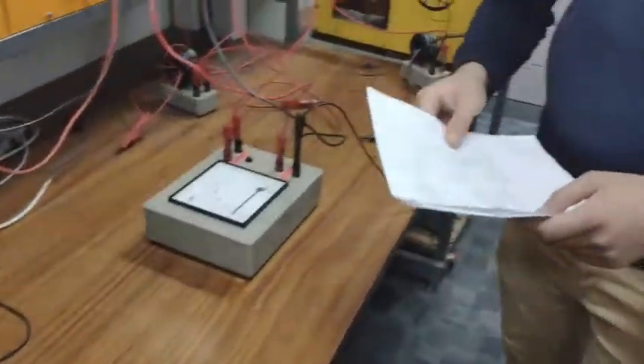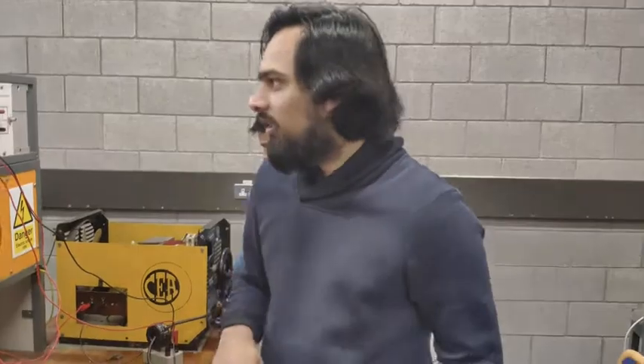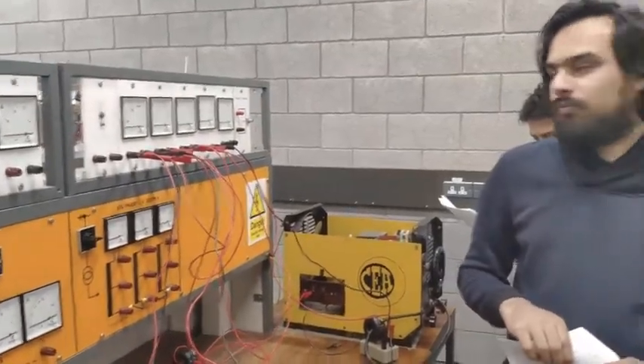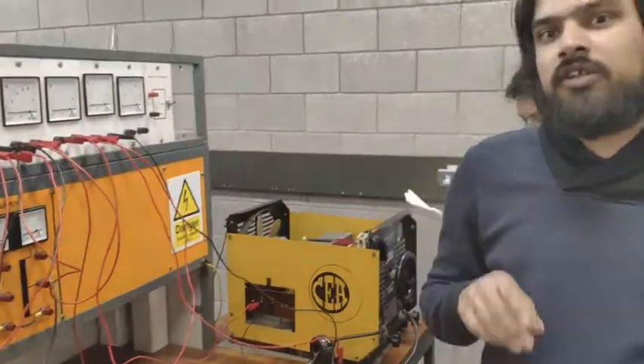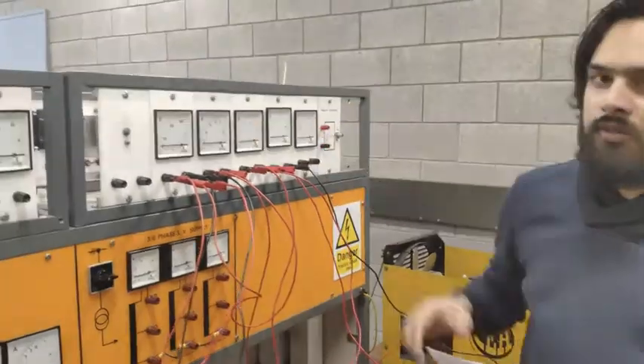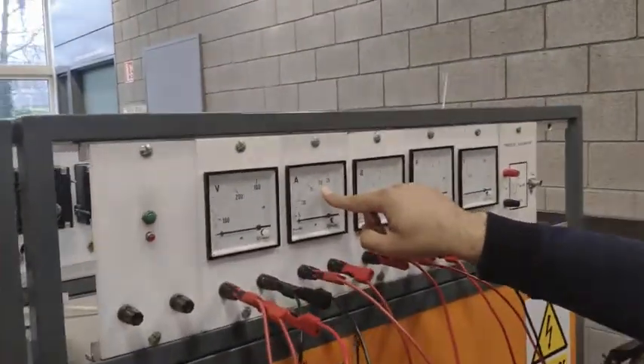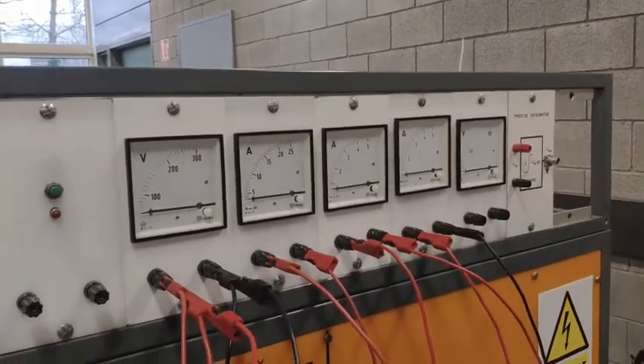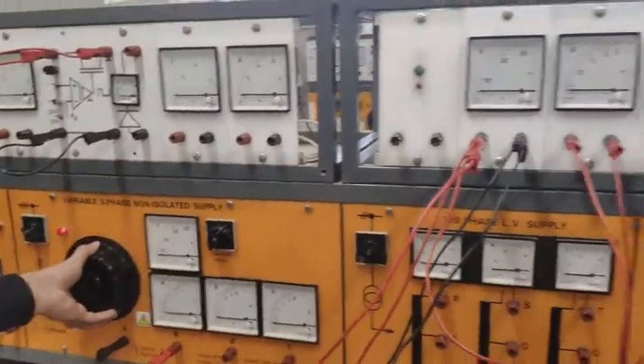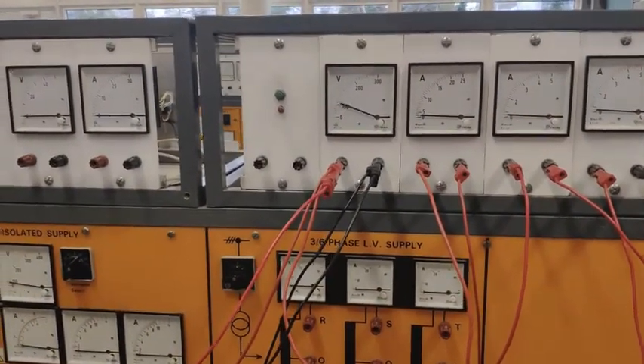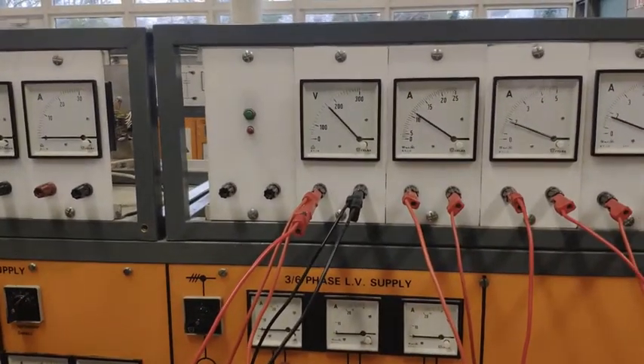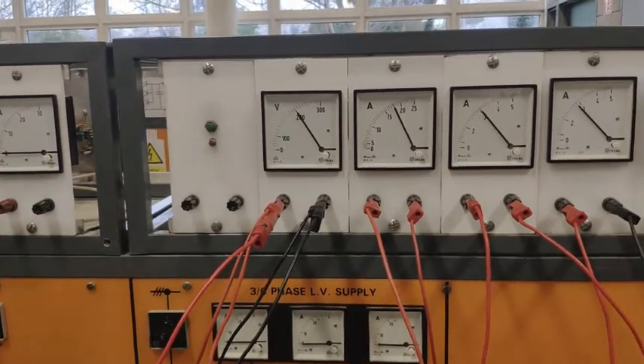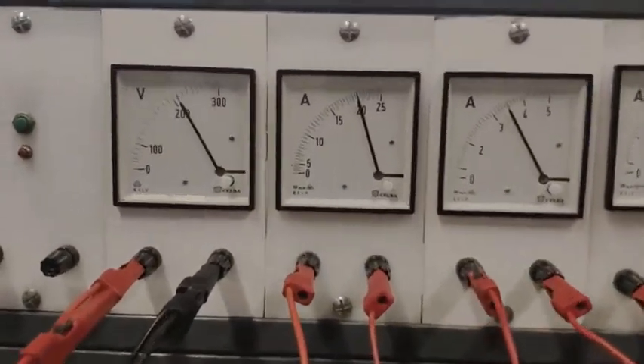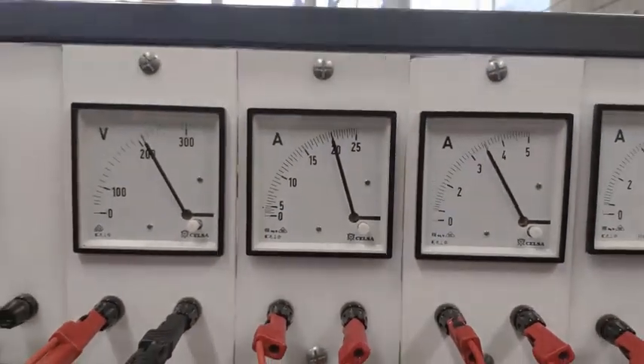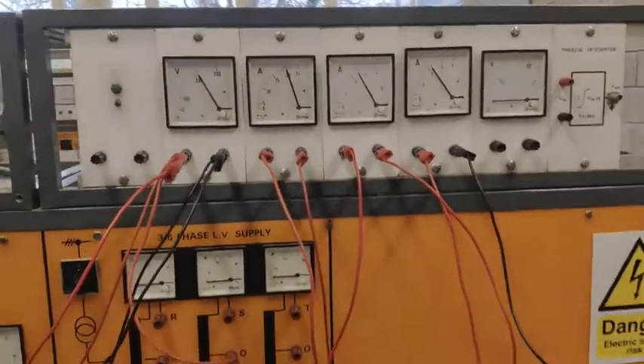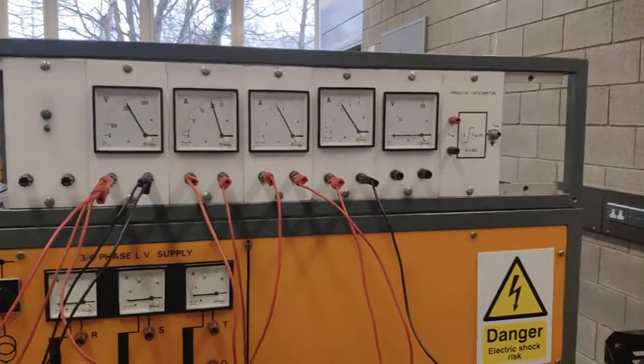You remember in the open circuit test, we applied 220 volts. Now this is a short circuit test, so we have to apply the rated current. In the open circuit, we applied the rated voltage. And my rated current is around 20 amps. So I will look at this meter, and I will increase the current little by little until I reach 20 amps.